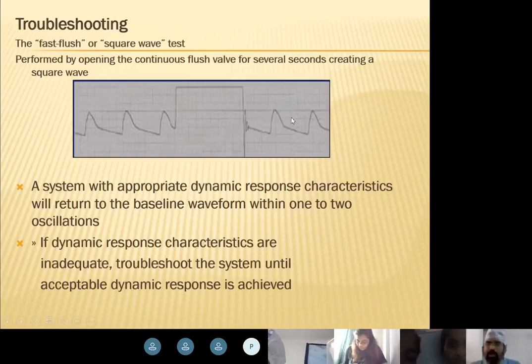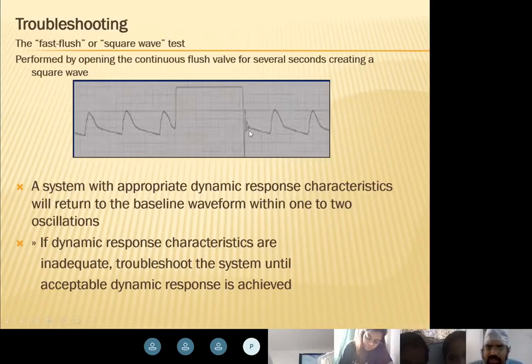So a normal or proper waveform will first go up, form a square wave, drop down, and then have two oscillations, one bigger than the other, one smaller than the other. So one oscillation, second oscillation, and back to the waveform. When you can see this kind of waveform during a fast flush, it means the dynamic response characteristics are adequate. That means this arterial line is okay and your patient's blood pressure has actually fallen. You don't have to flush this again. It is not an overdamped waveform.